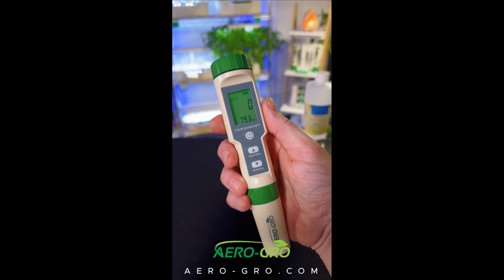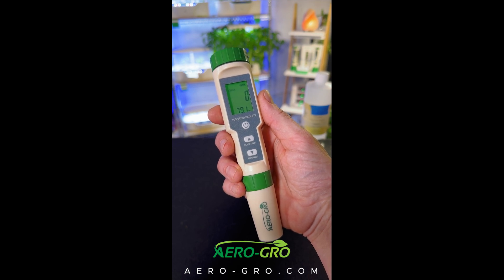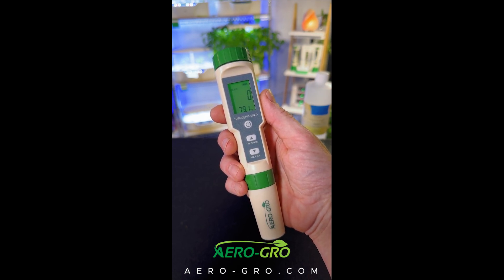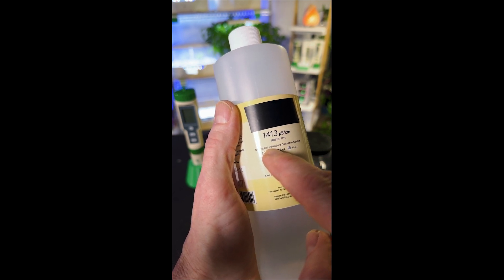Hey there growers! If you'd like to recalibrate the EC function on your Aero-Gro 5-in-1 meter, it's super easy and takes less than a minute — here's how you do it. You'll need to purchase some 1413 recalibration standard solution. I've provided a link below.